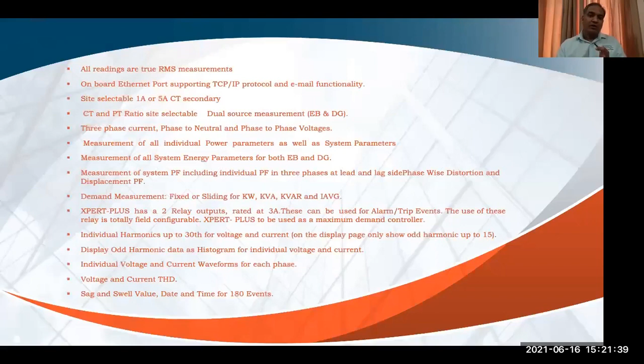This meter also records your neutral current, voltage phase angle, current phase angle, angle between voltage and current, voltage imbalance, current imbalance. It's a dual source meter and it has two relay contacts as well. So there are two programmable relay contacts to control your demand. You can set those relay contacts whether you want to just generate an alarm on any of the relay or you want to trip straight away.